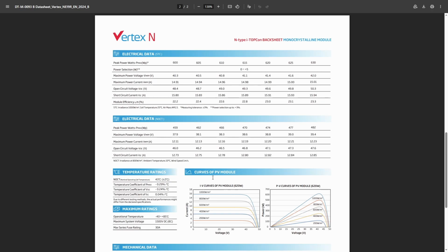This is why maximum voltage matters. Ignoring this can cause problems. You might exceed controller limits, even if the system looks fine on paper. If you only design using STC, you'll expect too much power, and too much voltage. If you ignore cold weather voltage, you risk damaging equipment. These numbers describe a range, not a single value.